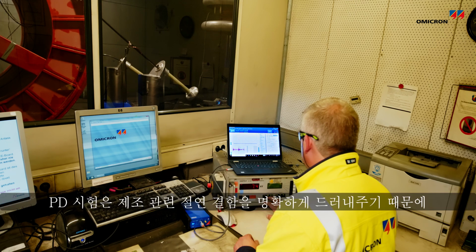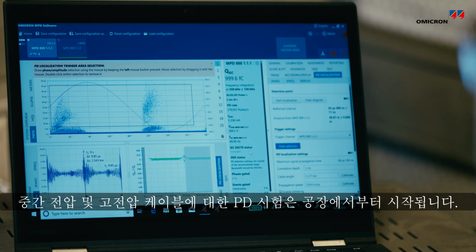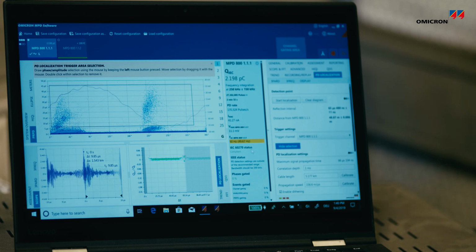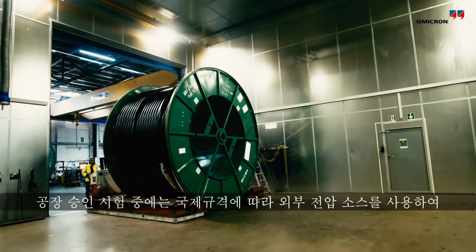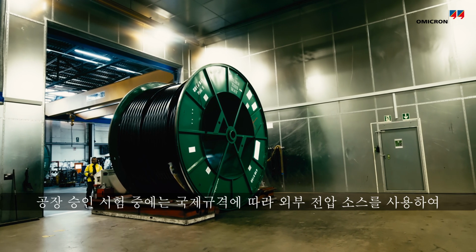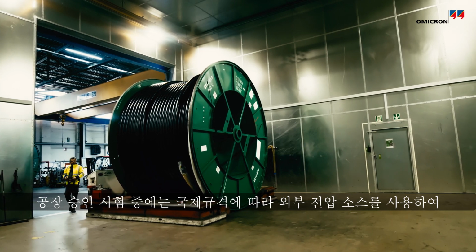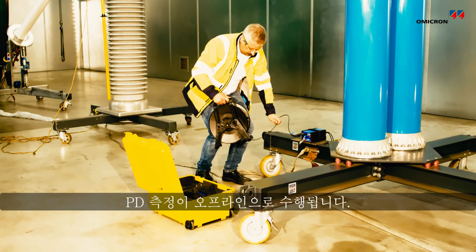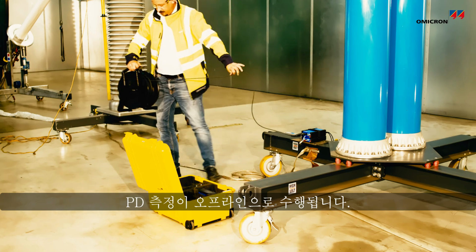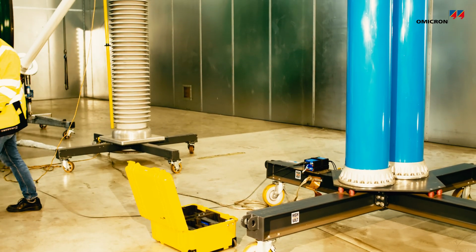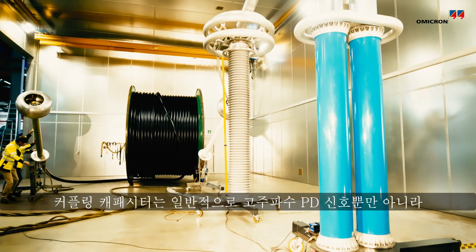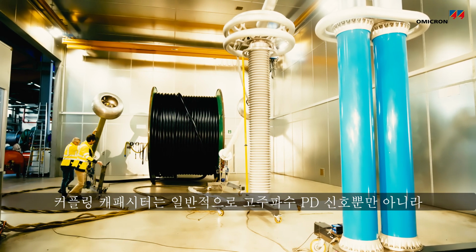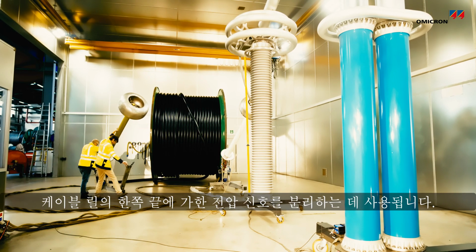PD testing on medium and high voltage cables starts in the factory, since it clearly reveals manufacturing-related insulation defects. During factory acceptance testing, PD measurements are performed offline according to international standards with an external voltage source. A coupling capacitor is typically used to decouple the high-frequency PD signals as well as the applied voltage signal at one end of the cable reel.